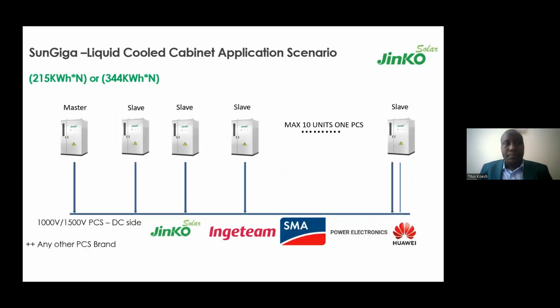From the current scenario, one of the battery cabinets, either 215 kilowatt hours or 344 kilowatt hours, acts as the master battery cabinet. We can then add other slave cabinets of either 215 or 344, based on the voltage range required, rather the input voltage range of the PCS.